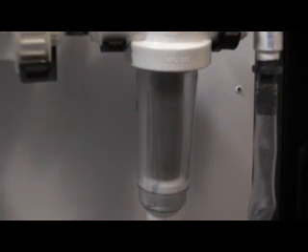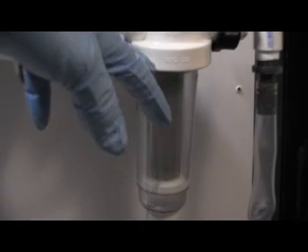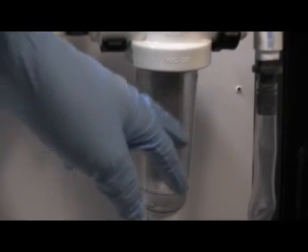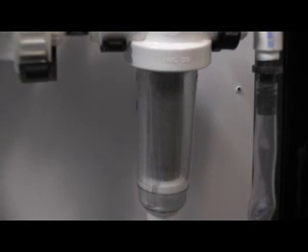Now you might be wondering, why the strainer? Okay, calcium is a solid. It's the binding agent of the chlorine molecule, and so ideally you would want the tablet to dissolve completely, but sometimes with this unit design, it doesn't have complete dissolving of that tablet. So that strainer there is to catch the suspended particulates of a specific diameter. That screener is designed to take particulates of a certain micron size and separate them from the water.